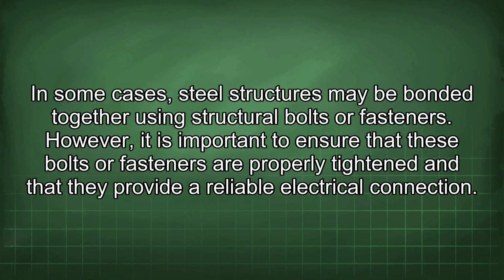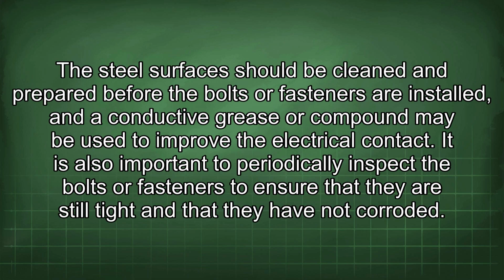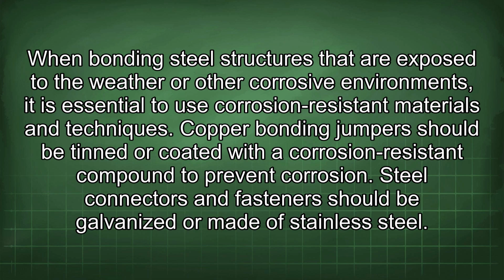In some cases, steel structures may be bonded together using structural bolts or fasteners. However, it is important to ensure that these bolts or fasteners are properly tightened and that they provide a reliable electrical connection. The steel surfaces should be cleaned and prepared before the bolts or fasteners are installed, and a conductive grease or compound may be used to improve the electrical contact. It is also important to periodically inspect the bolts or fasteners to ensure that they are still tight and that they have not corroded. When bonding steel structures that are exposed to the weather or other corrosive environments, it is essential to use corrosion-resistant materials and techniques.